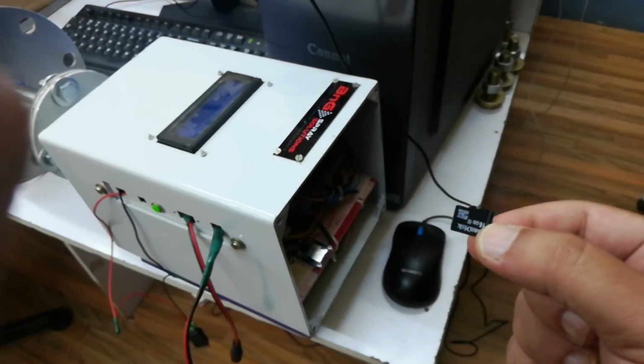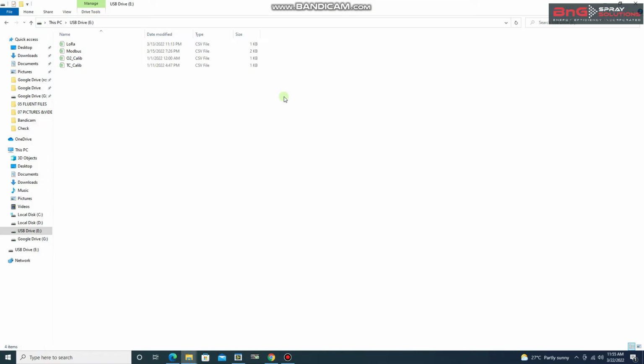Okay, so here we open the SD card that we just removed from the oxygen analyzer. As you can see, there are 4 different files in this. For the TC calib, you don't need to do anything. This is something which is recorded when the thermocouple is calibrated. But the 2 main files of interest would be the Modbus and the oxygen calibration file. The LoRa also, you don't need to make any changes to it.